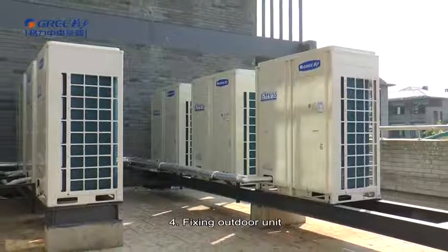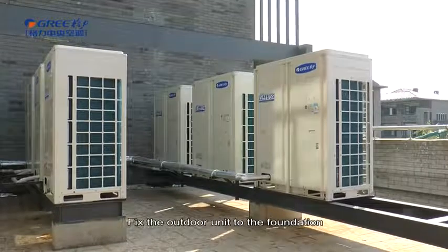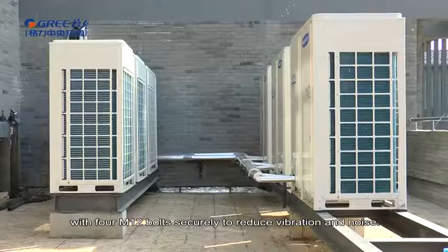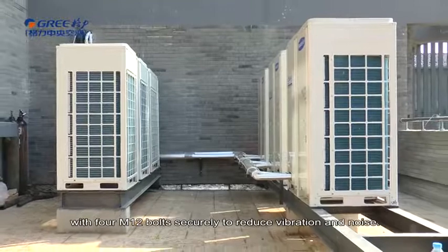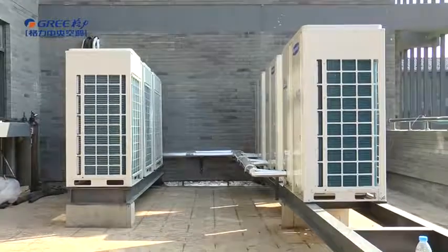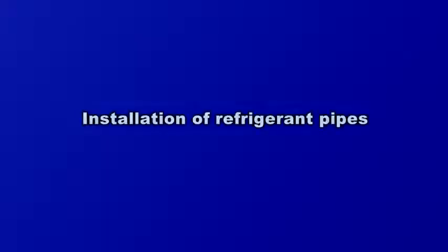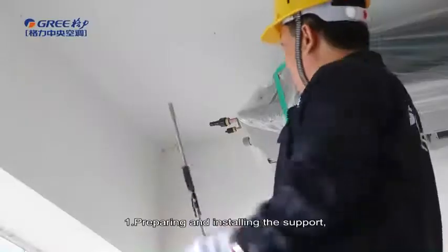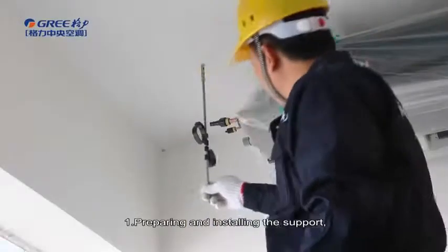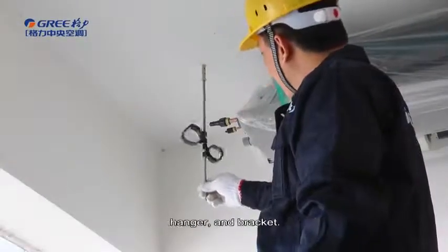Fourth, fixing outdoor unit. Fix the outdoor unit to the foundation with 4 M12 bolts securely to reduce vibration and noise. Installation of refrigerant pipes. Steps to install the refrigerant pipes are as follows. First, preparing and installing the support, hanger, and brackets.